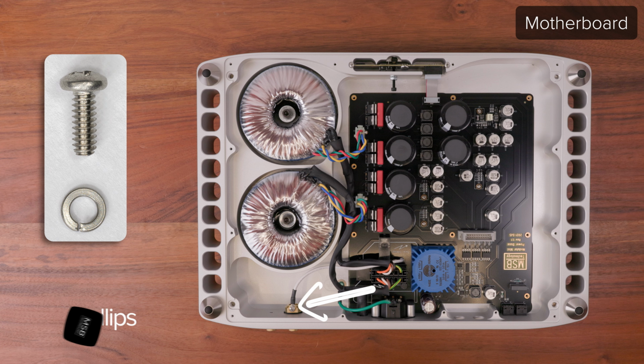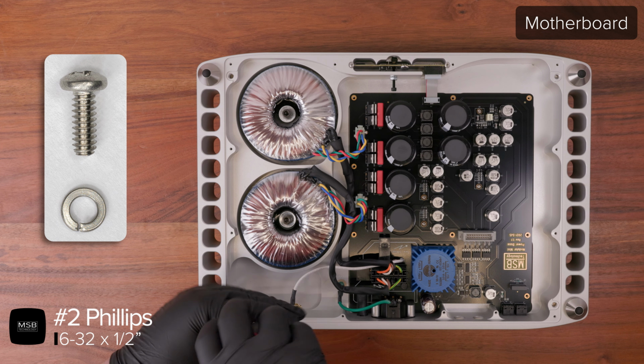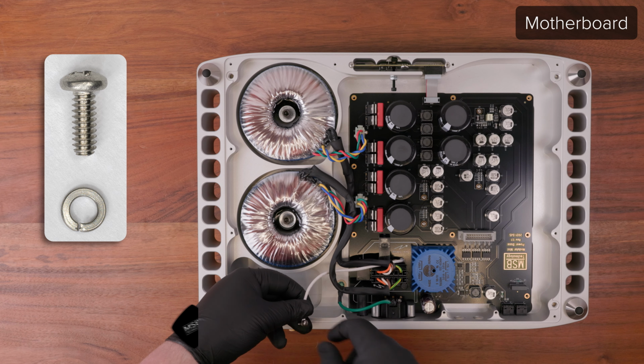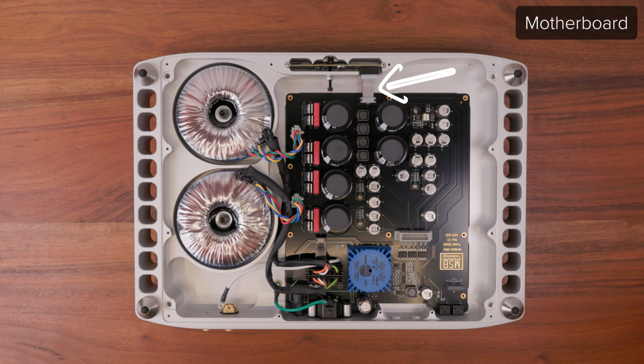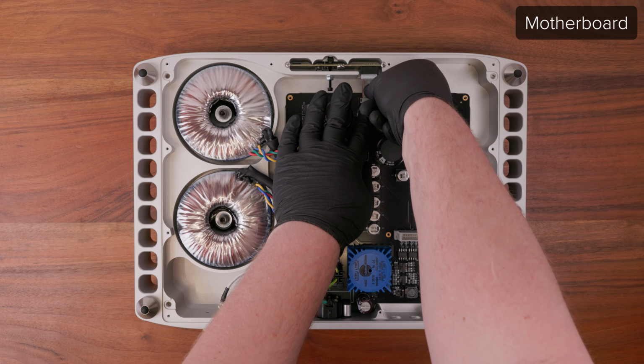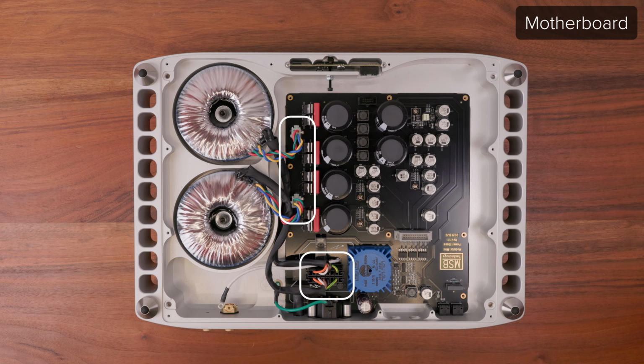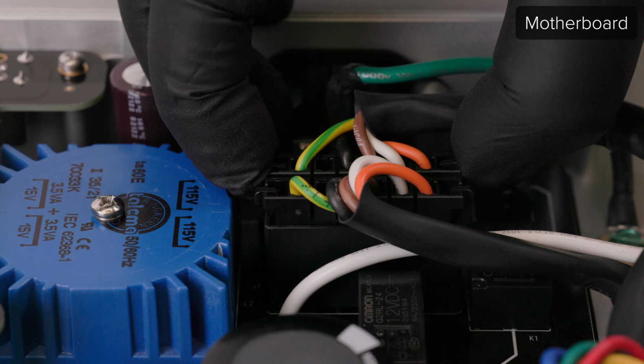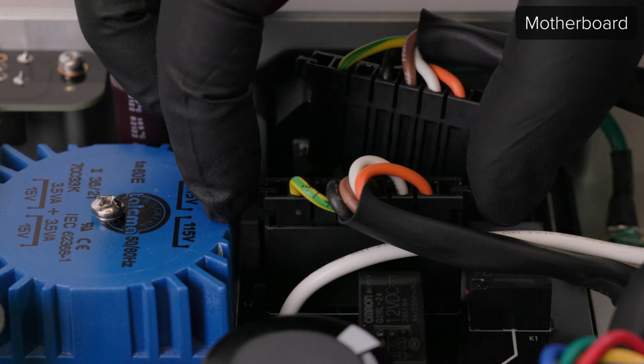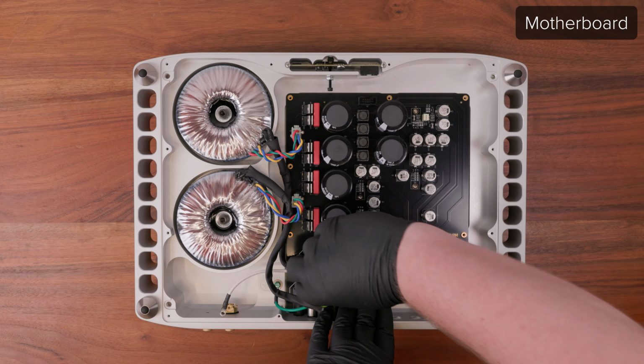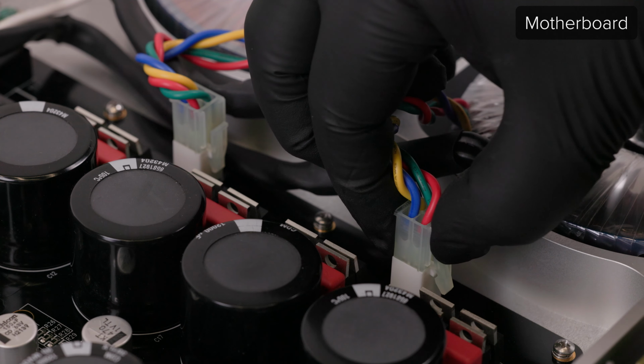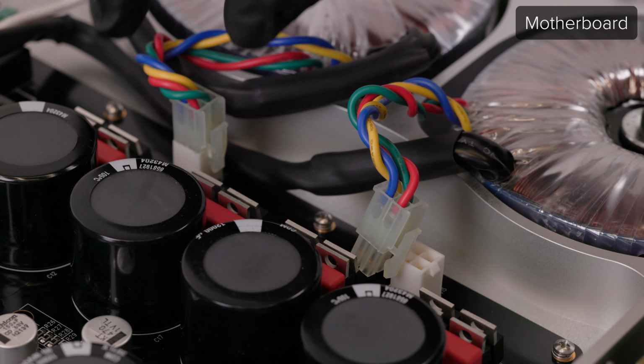Use a No. 2 Phillips to remove the 6-32 screw from the grounding lug. Remove the ribbon cable from the front control board. Then disconnect all 4 of the transformer connectors. The black ones require you to squeeze both ends of the connector to unplug them. The white connectors can be removed by pinching the release tab on the side.